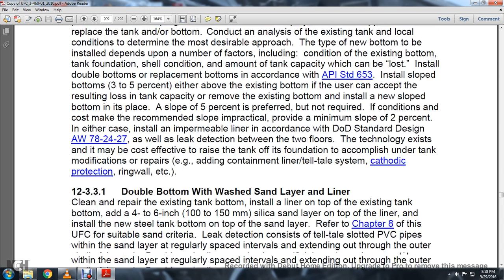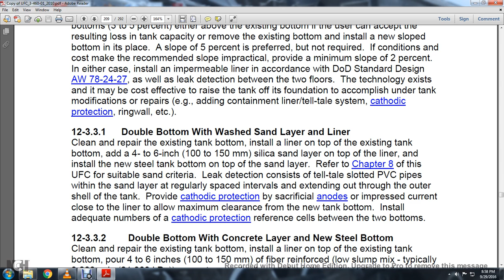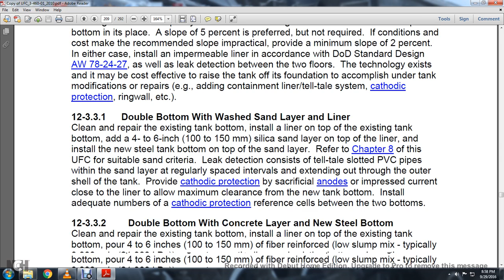Refer to UFC suitable sand criteria. Provide leak detection consistent with telltale slotted PVC pipes within the sand layers, regularly spaced at intervals extending out through the outer shell of the tank. Provide cathodic protection, sacrificial anodes or impressed current, close to the liner with the maximum clearance within the tank bottom, and install an adequate number of cathodic protection reference cells between the two bottoms.